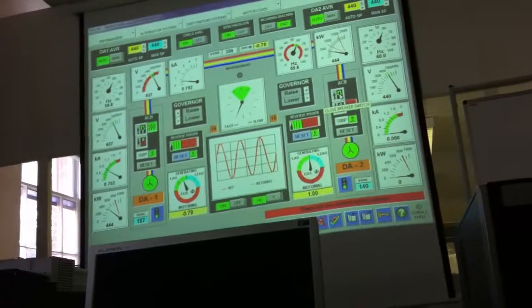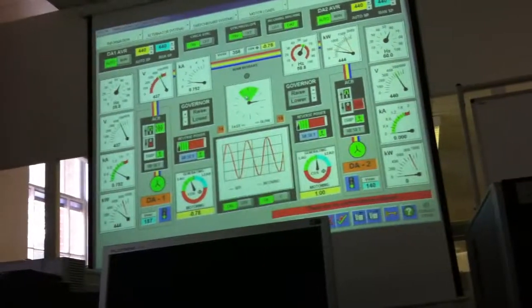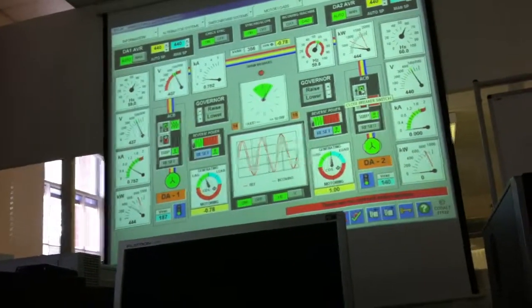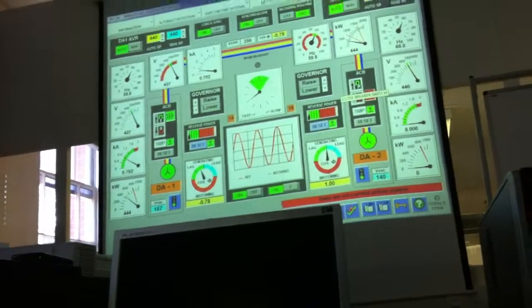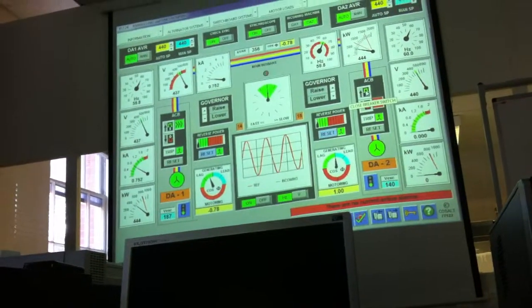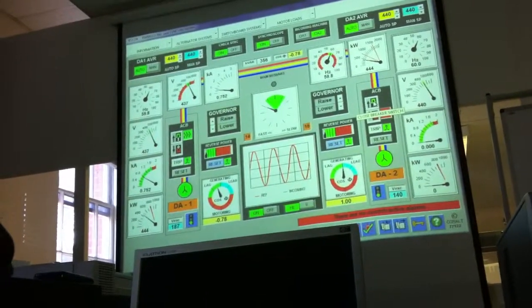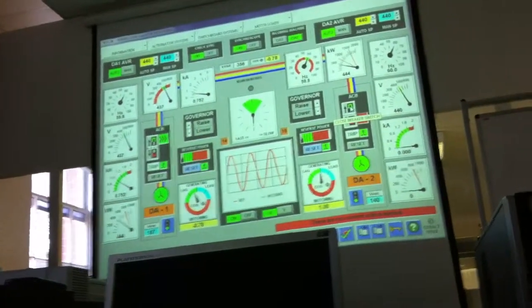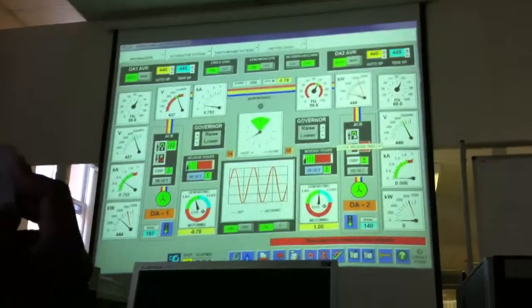So again, one of the key things here is getting the timing. And we need to press the breaker at 5 to 12. Now here, explain why. And if we leave it to 12 o'clock, we're too late. Because we have to consider our reaction time of our finger and also the breaker physically moving. And it's a very fast reaction.